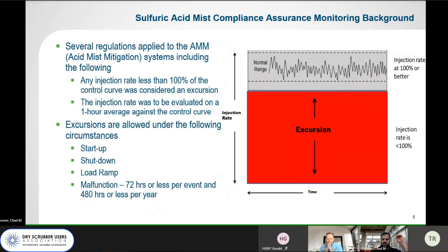That led to a number of other issues. Again, there's several regulations that applied to the operation of these, they call it acid mist mitigation systems. So again, their original was ammonia, and then they included the hydrated lime under that. But some of the rules for operating the system were any injection rate less than 100% of the control curve was considered an excursion. The injection rate was to be evaluated over a 1 hour average.